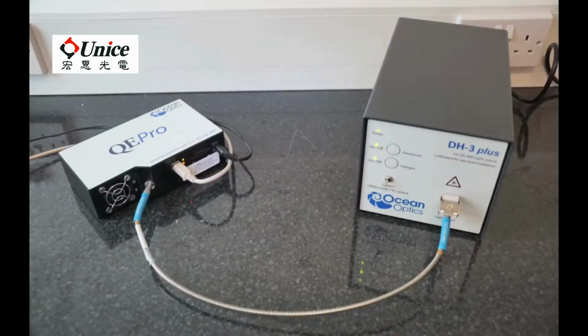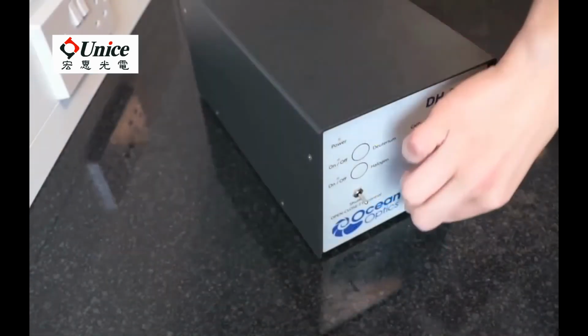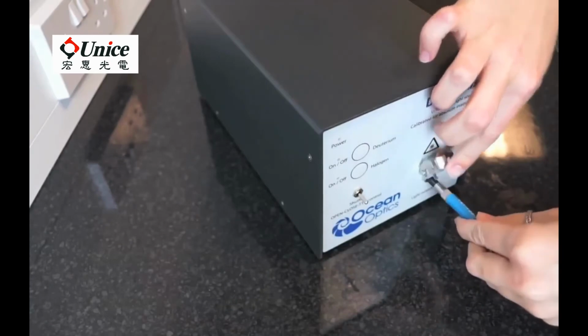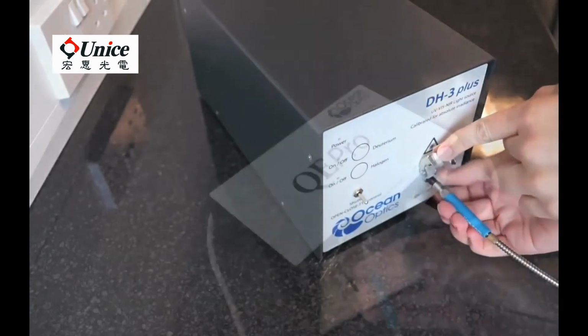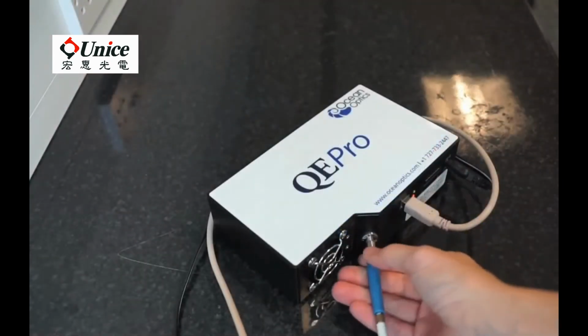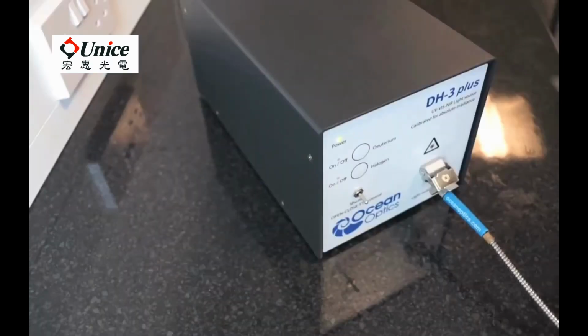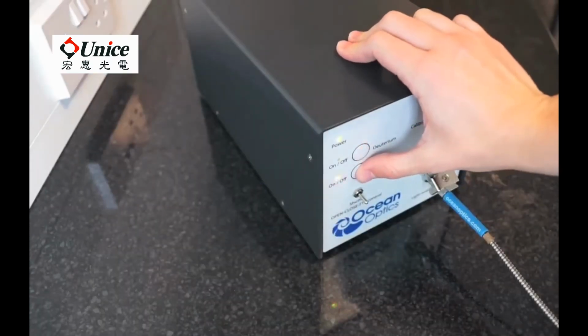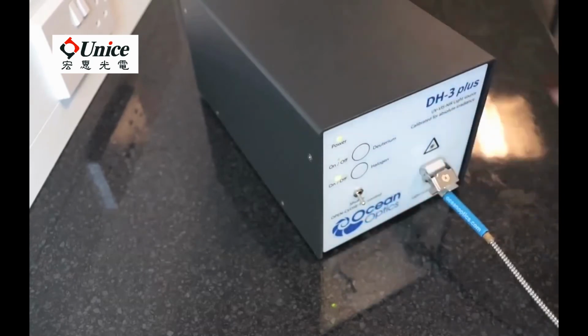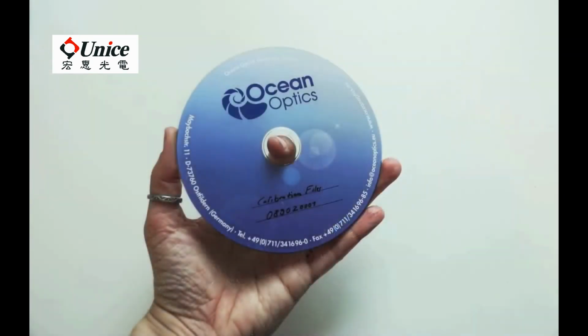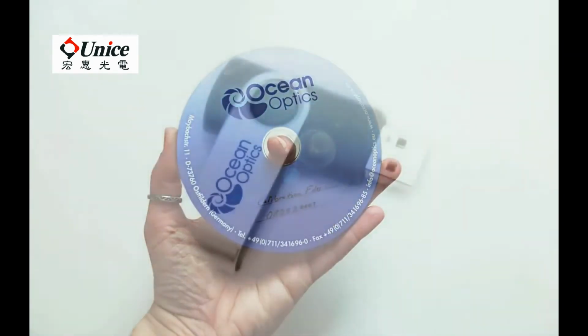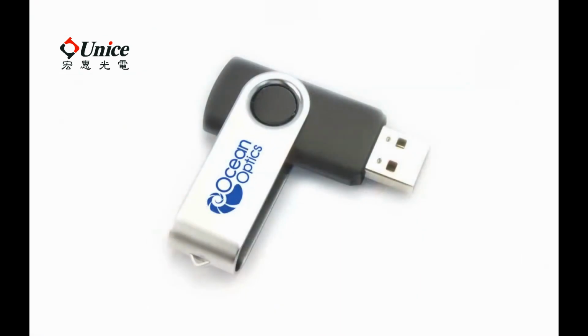It's vital to make sure that your configuration is the same as what you'll use for your measurements. Once you have done the calibration, you must stick with this configuration and not dismantle it, as the system will need recalibrating. To set up the equipment, simply attach each end of the fiber to the light source and the spectrometer. Turn on your light source and allow it to warm up for 20 minutes. You should insert the CD or USB drive containing the calibration data that came with your calibration lamp.